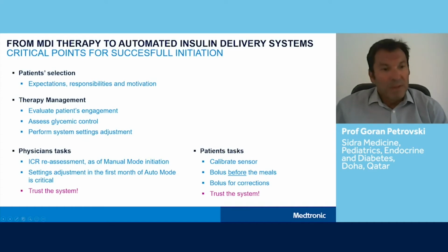What about therapy management? We need to evaluate patient engagement. So we want our patients to use the sensor more than 80–85% of the time and to stay in auto mode, because if the patient is staying in auto mode, we will have better control. We need to evaluate the glycemic control, both A1C and the time in ranges. And we need to perform the system settings. Compared with the previous pumps, this is much easier because we only need to change the carb ratio if needed. So there are also physician tasks and patient tasks.